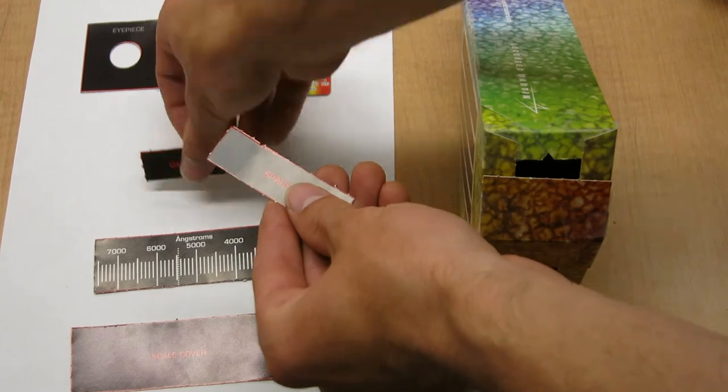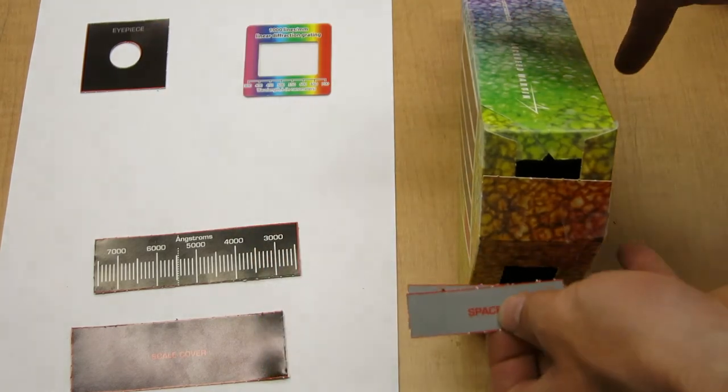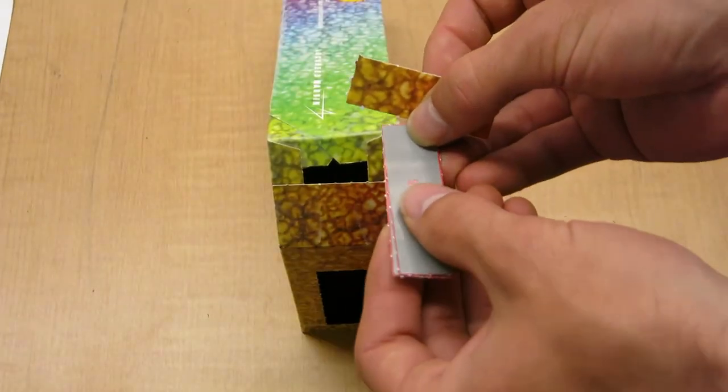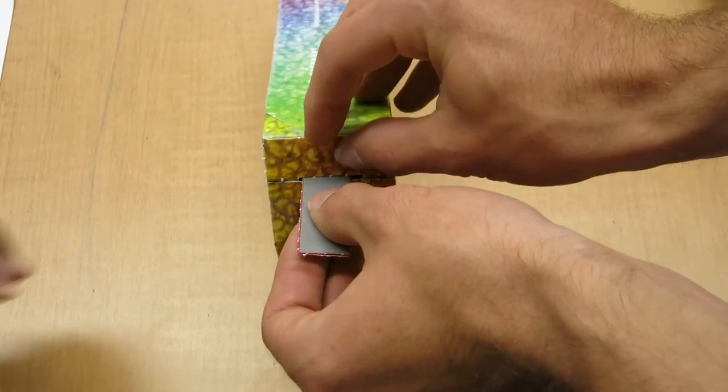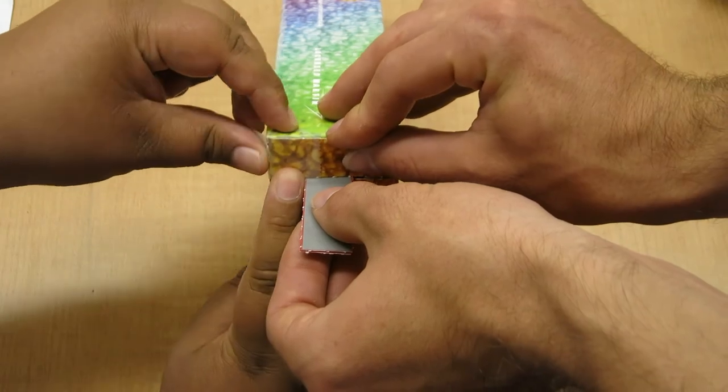Now we'll create the entrance slit. Use two spacers stacked on top of each other to set its width. Once you have it set at the right width and parallel, tape it down.